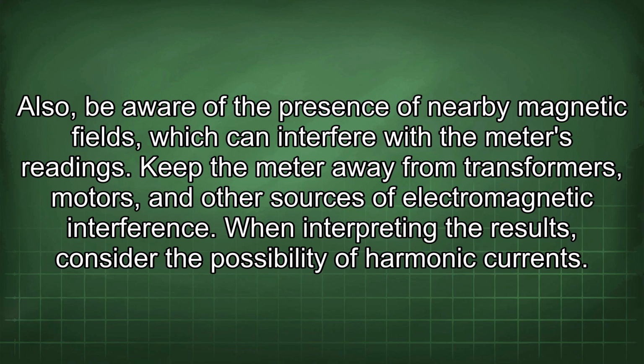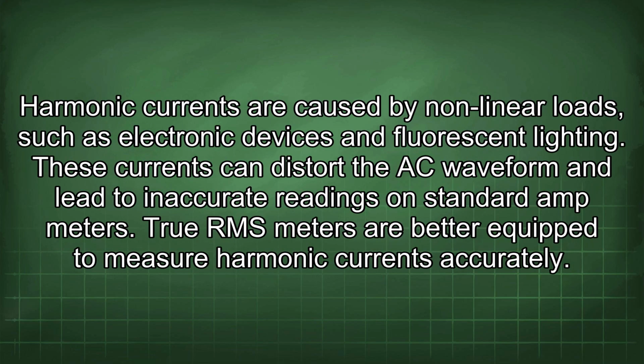When interpreting the results, consider the possibility of harmonic currents. Harmonic currents are caused by nonlinear loads such as electronic devices and fluorescent lighting. These currents can distort the AC waveform and lead to inaccurate readings on standard ammeters. True RMS meters are better equipped to measure harmonic currents accurately.